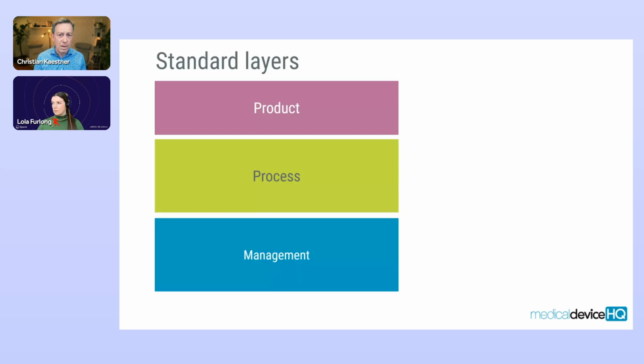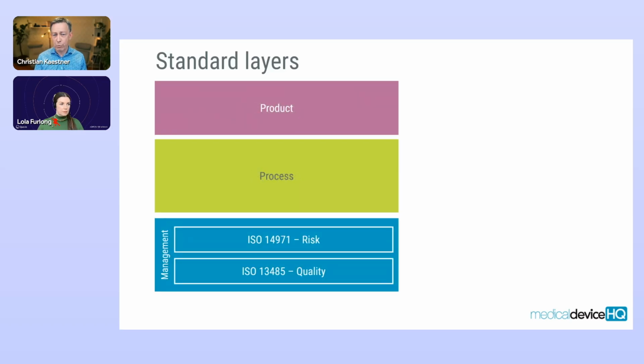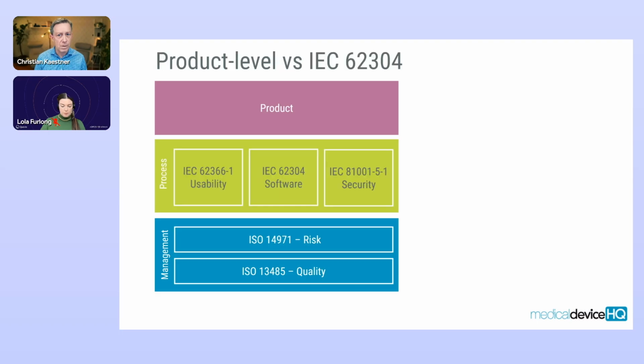I typically divide standards into three groups: product, process, and management standards. The management standards are process standards or groups of process standards applicable to all kinds of medical devices and include quality and risk management standards. In a process group, you find standards relevant to the product you're developing, which vary depending on the product. If we assume software is part of a medical device, I would expect to see standards covering areas such as usability, software, and security. Please note that at this stage, there's still no significant difference in the type of software you develop.